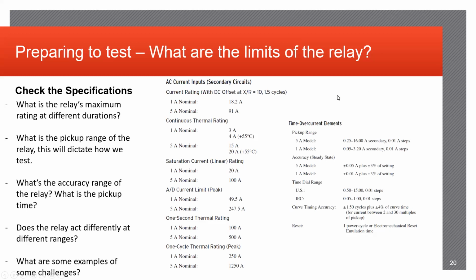So going on the AC side, you want to look at the relay manual and the specifications to identify what the max current ratings, voltage ratings, pickup ranges may be prior to setting up your test plan or injecting any values. You want to determine the accuracy range for testing purposes as well. Does the relay act differently at different ranges? This could be extremely important, especially for time over current elements. And other examples such as thermal ratings, saturation currents, continuous thermal ratings, et cetera.